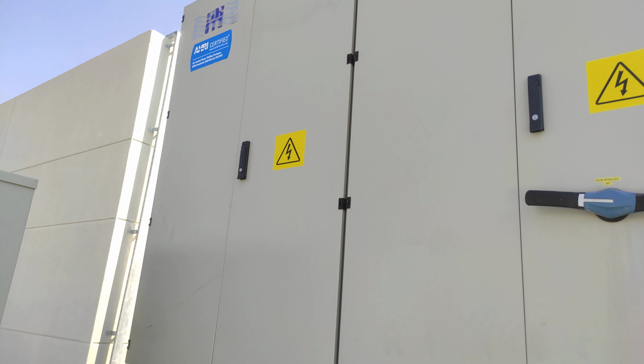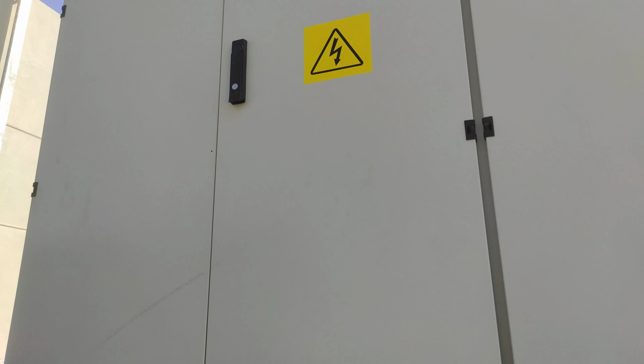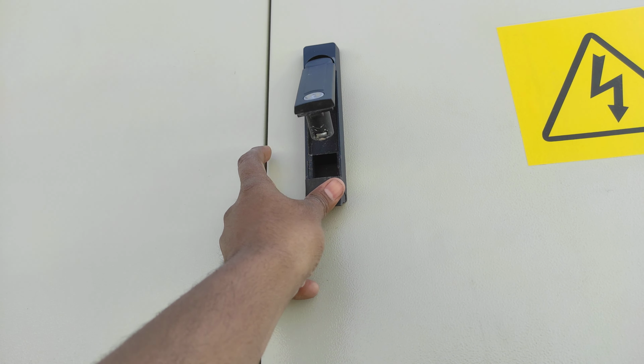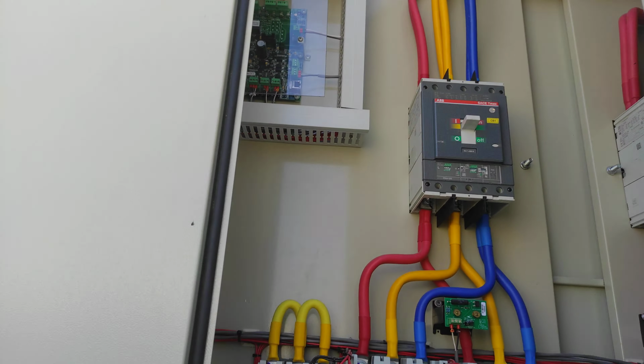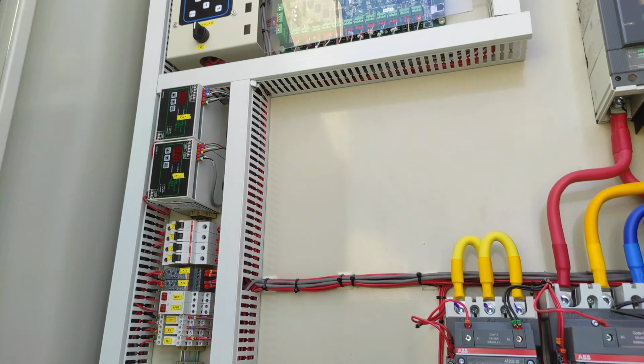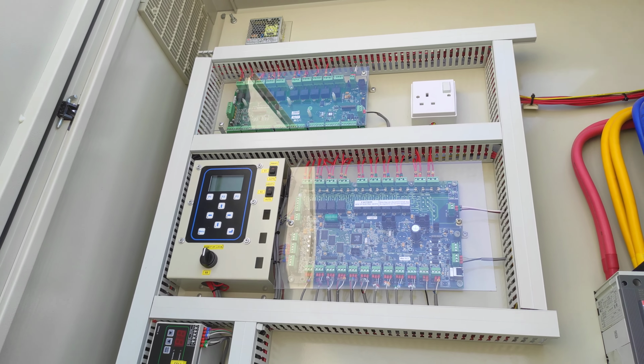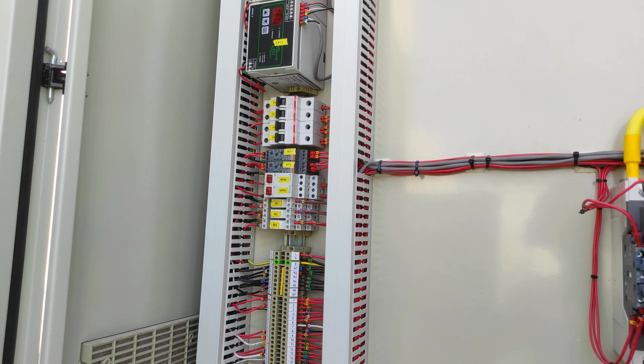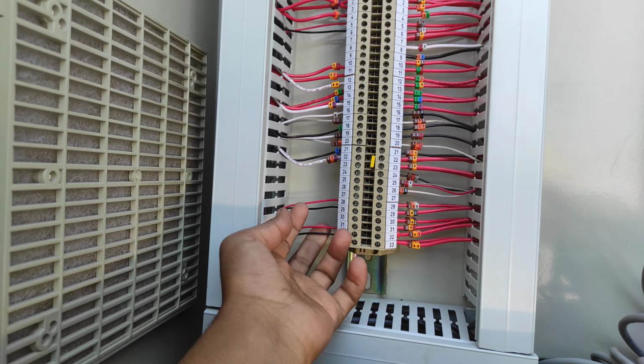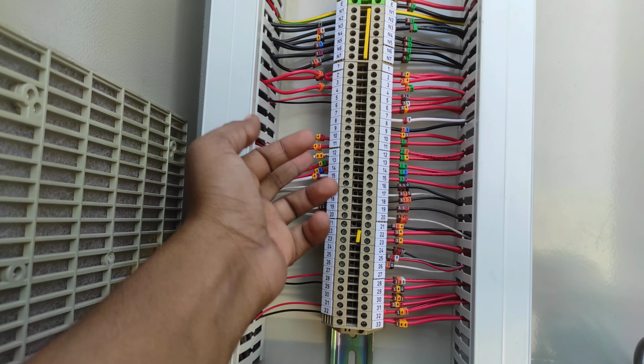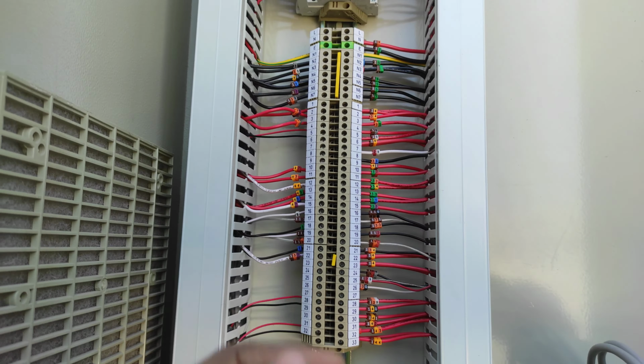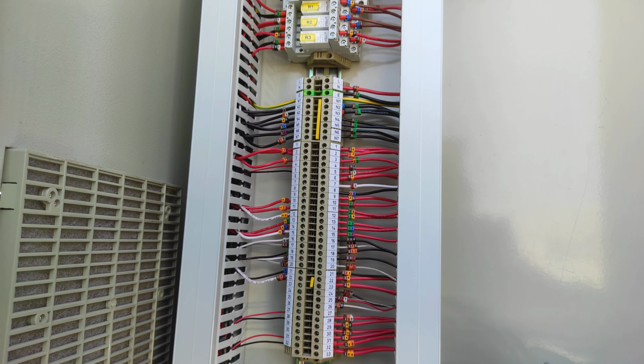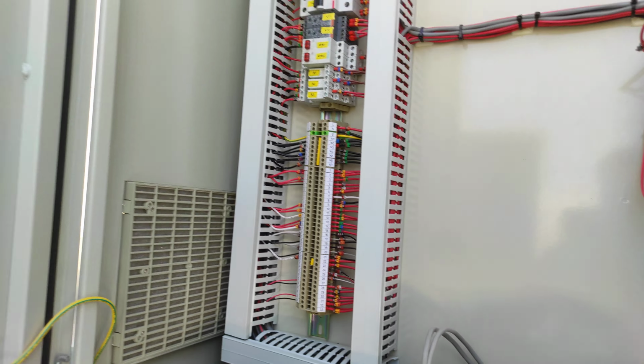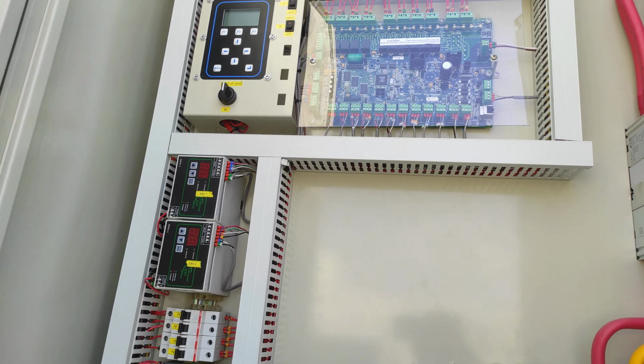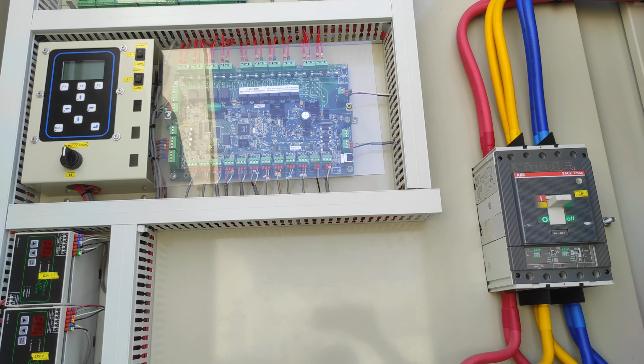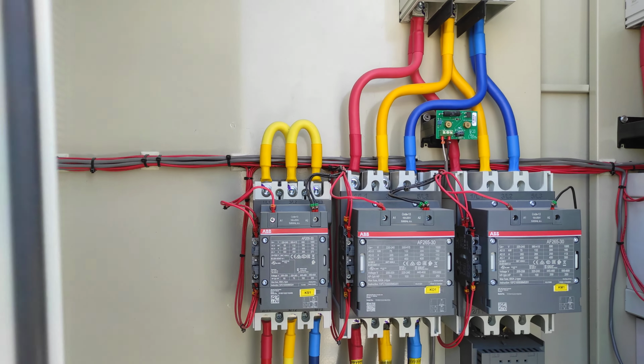I will show you the control panel also. This is the whole control panel. You can see here, for operation we have used like 31, 32, 27, 28 and this 4, 5. For on and off, for the tripping, for the signaling, feedback, we have used the connections from this also. This is the whole control panel for the cooling tower operation. These are the starters.